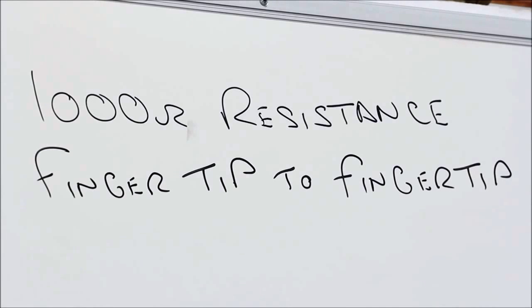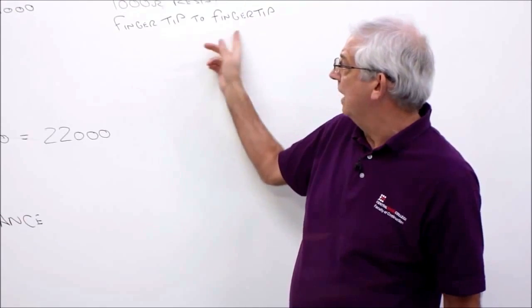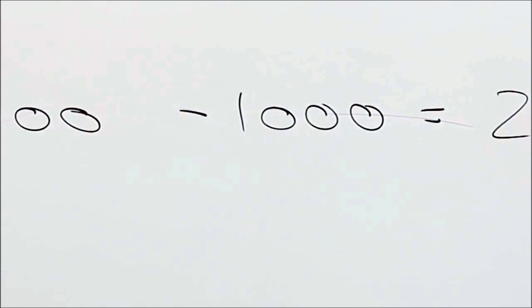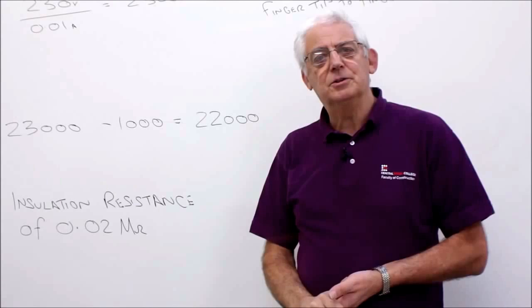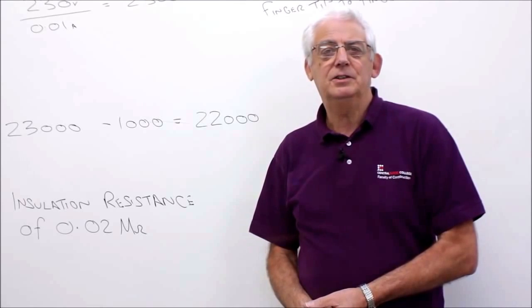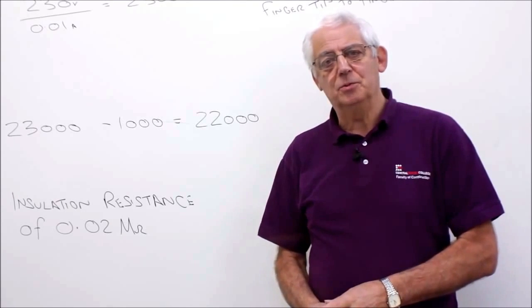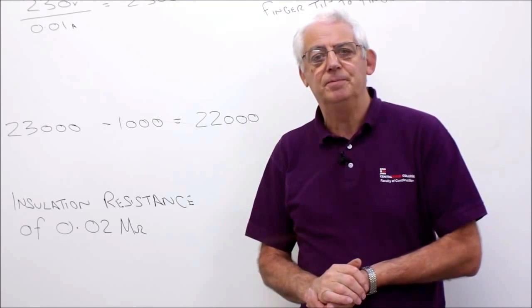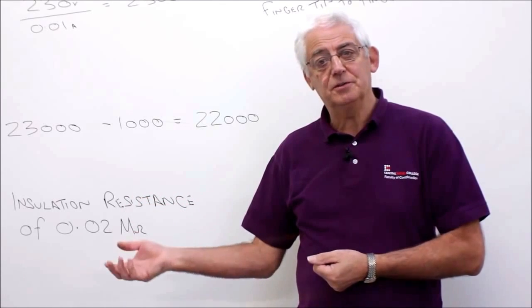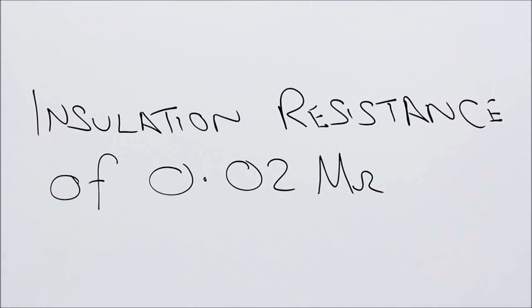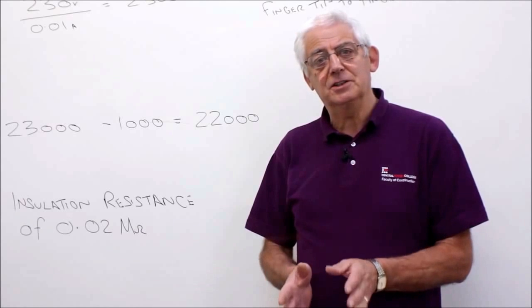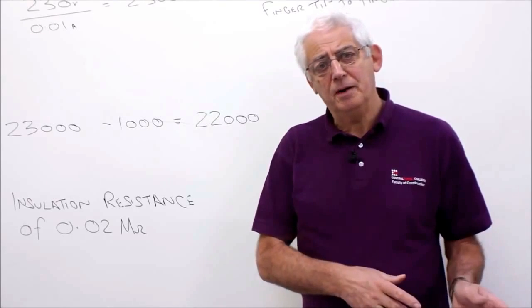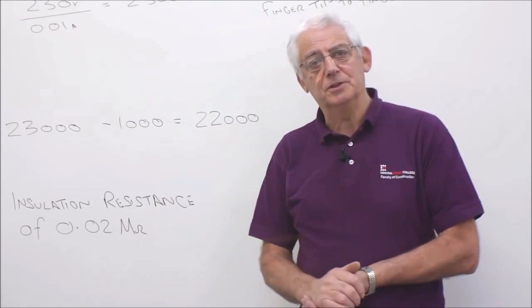Now, what the regulations also tell us is that from fingertip to fingertip, we have a resistance of 1,000 ohms. So we can subtract the 1,000 ohms from our 23,000 ohms, which would leave us the maximum resistance permitted between a known earth and the piece of metal which we're trying to test. That's a difficult value to measure with a normal low resistance ohm meter, so we're going to use an insulation resistance tester. Of course, the insulation resistance tester won't measure very accurately, but it will give us an indication. So if we measure between our known earth and the piece of metal which we're not sure wants bonding or not, if we get a value of 0.02 megohms, which is 20,000 ohms or less, then it is an extraneous conductive part and it should be bonded. If we get a value of above 0.02 megohms, then it's just a piece of metal.